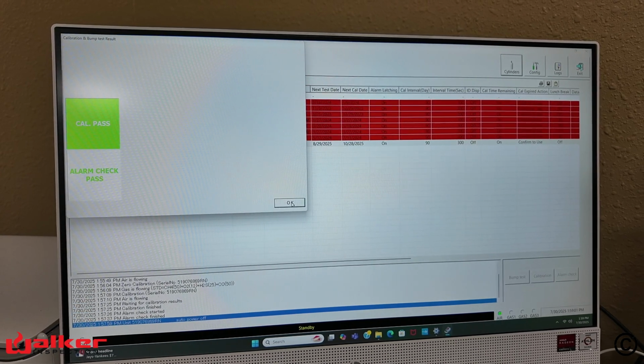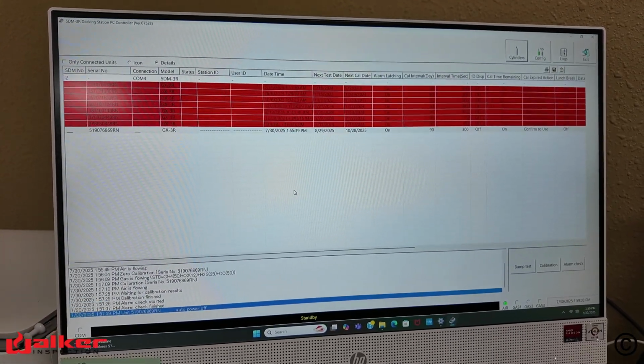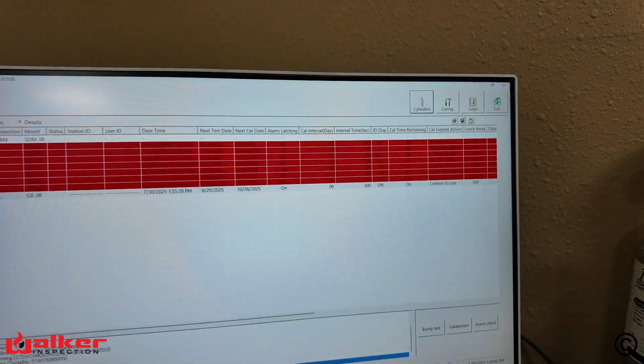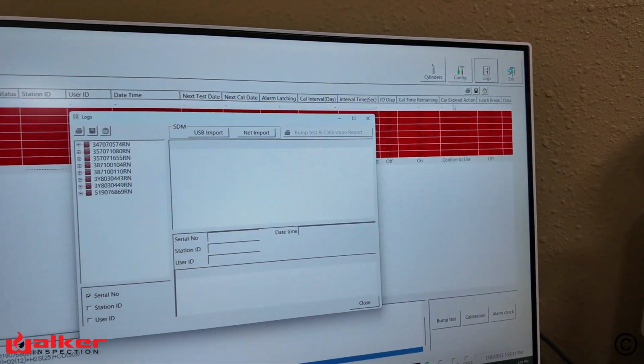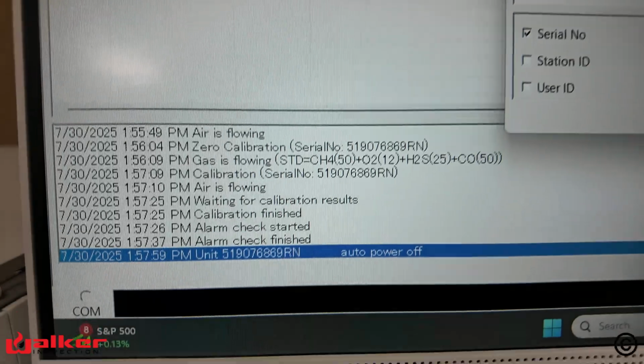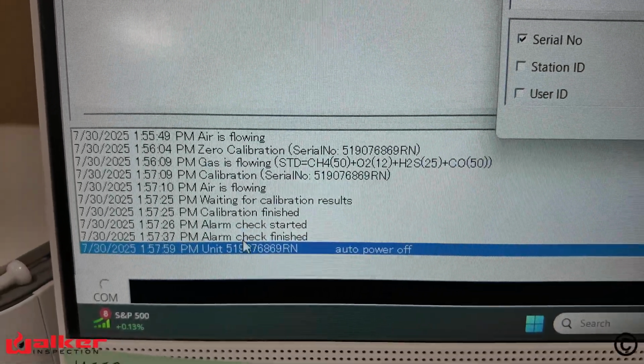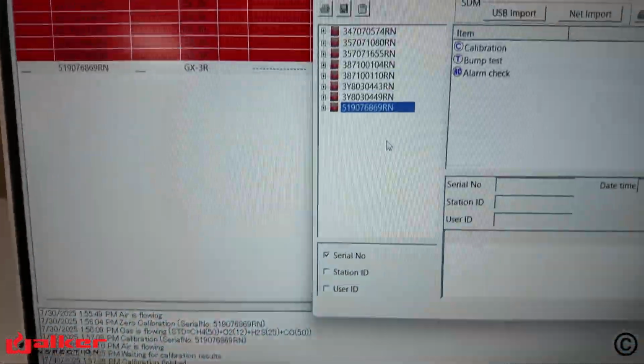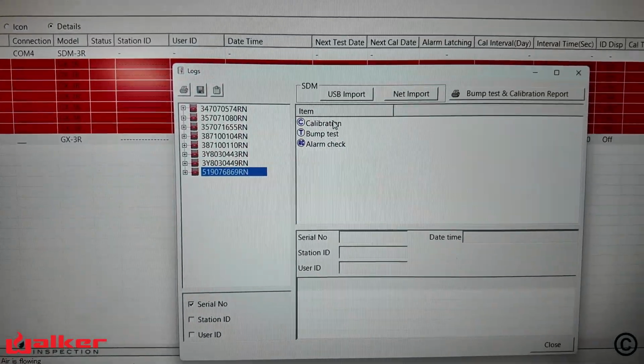It also tests the alarm system, which should say Alarm Pass in blinking green as well. Once we get Calibration Pass, the calibration sheet needs to be printed off. In order to do that, click the Log button on the top right-hand side. Double-click the correct serial number, which can be seen on the original screen. Then double-click the correct year and month. This will display the page to print.